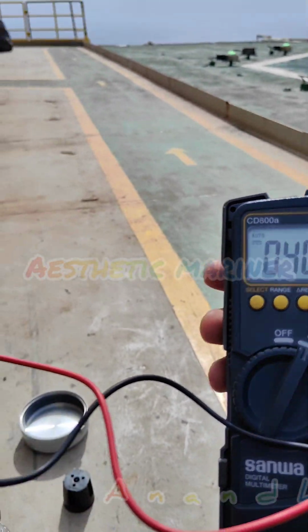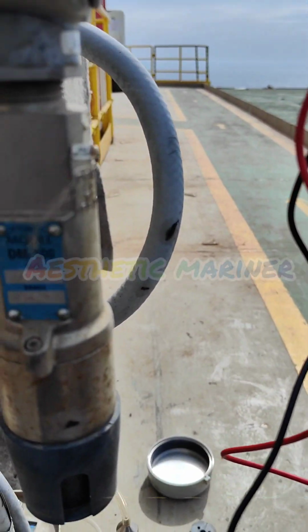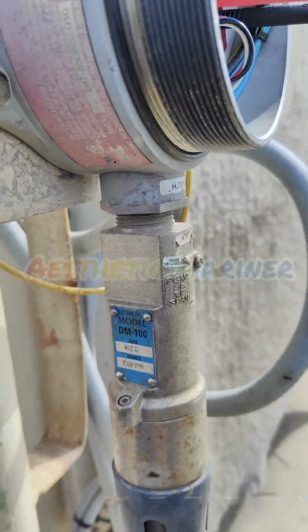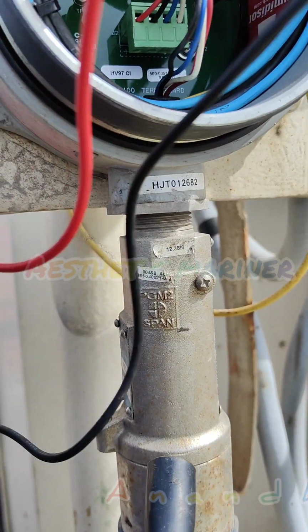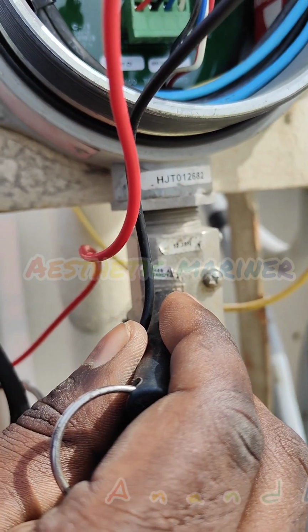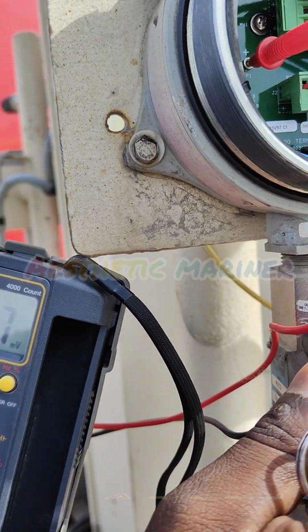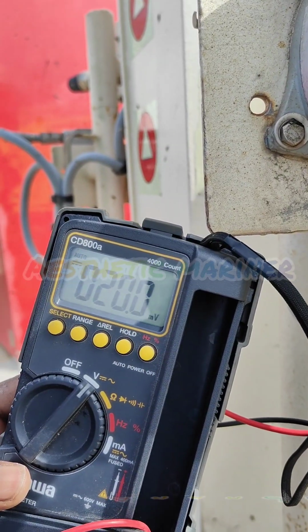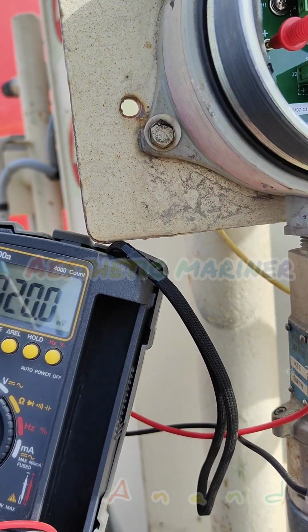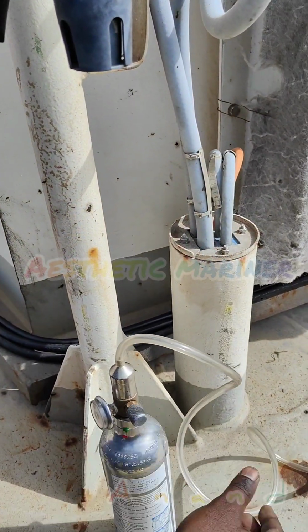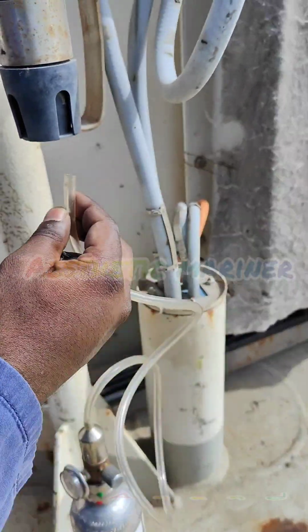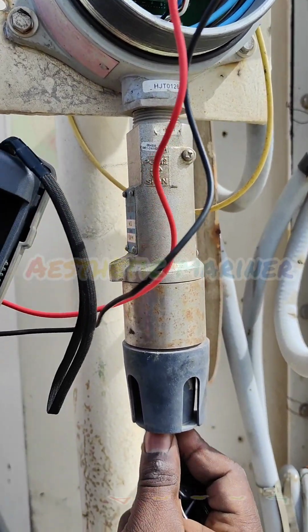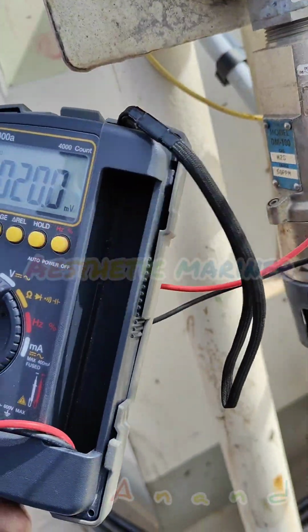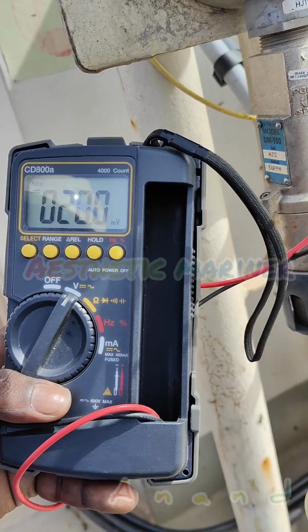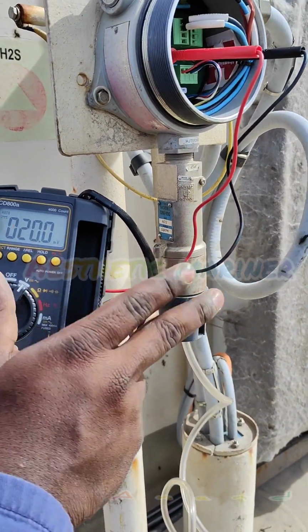In this multimeter, you can see 40 millivolt. It means 0 ppm is there, so we need to do the zero calibration. Then we hold the magnet on PG2 for the span calibration. Once it goes into calibration mode, it will show 20 millivolt. If 20 millivolt comes, it means it is already in calibration mode. Then we apply the span gas, 25 ppm. Now we need to wait 2 minutes.